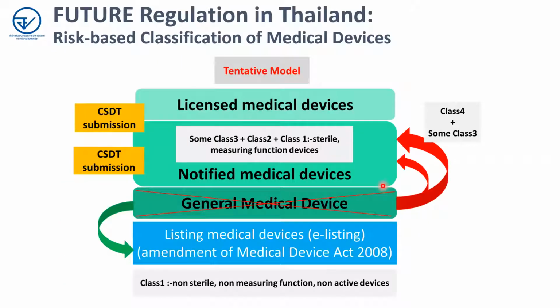And these are the future plans in Thailand. This is a tentative management rule. Right now, the license, notify and general medical device categories are quite policy based. Afterward, they will use a risk-based approach according to the AMDD. Most of class 4 and class 3 will become licensed medical devices, while class 2, class 3, and also some class 1 sterile devices will become notified. The other class 1 devices will become listing medical devices, just e-listing. So it will become this management model.